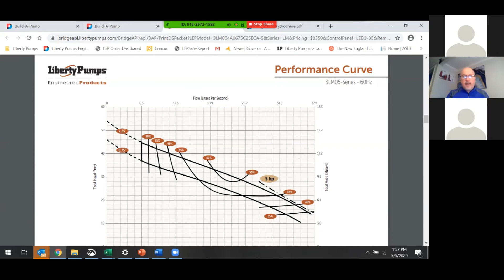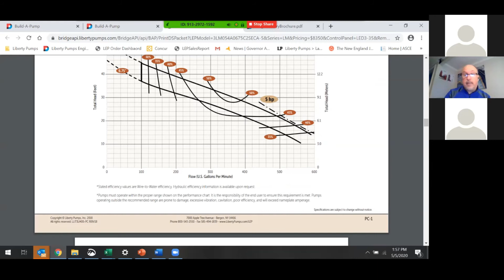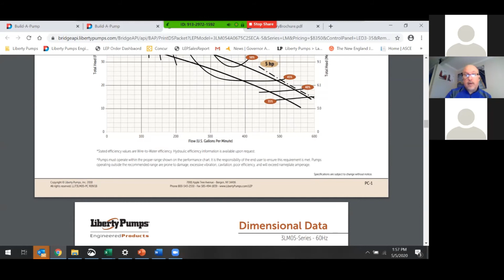These efficiencies are currently written as wire-to-water efficiencies, and we do have hydraulic efficiencies available too. We tried to go with where the industry is heading, which is toward wire-to-water efficiencies. However, many manufacturers still use hydraulic efficiencies, which can sometimes be 10 to 15% more efficient. So if there's ever an issue meeting a specific efficiency, we can double check and offer hydraulic efficiencies as well.